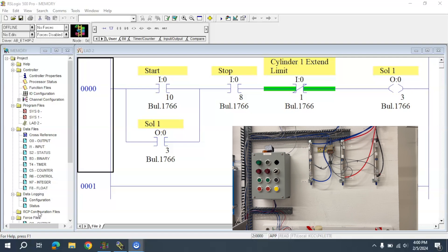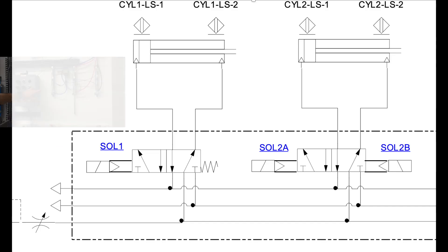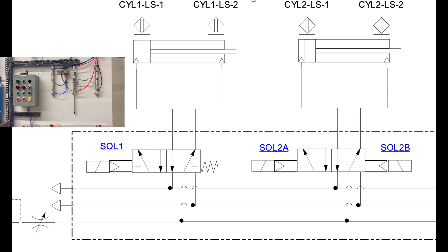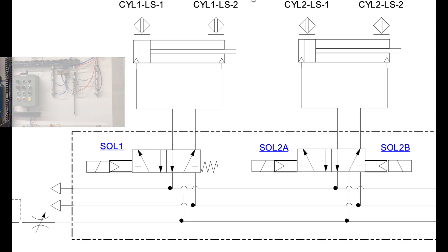How am I going to do that? Cylinder 1 is a 5-2 solenoid activated spring return. Cylinder 2 is double solenoid activated, so it doesn't need memory to stay in its desired position.